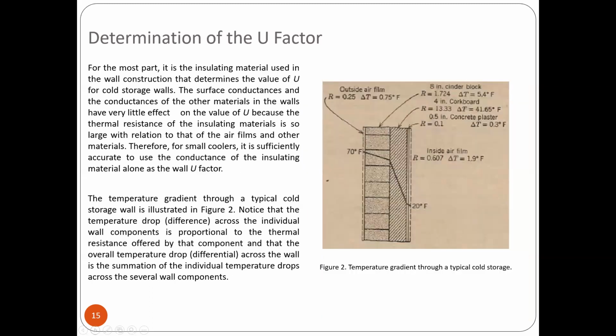Now, for the most part, it is the insulating material used in the wall construction that determines the value of U for a cold storage wall. So the surface conductances and the conductances of other materials in the wall have very little effect. So we can neglect them in the value of U because the thermal resistance of the insulating material is so large relative to that of the air film and other materials. Therefore, for small coolers, it is sufficiently accurate to use the conductance of the insulating material alone as the wall U factor. For small coolers, this is the temperature gradient.